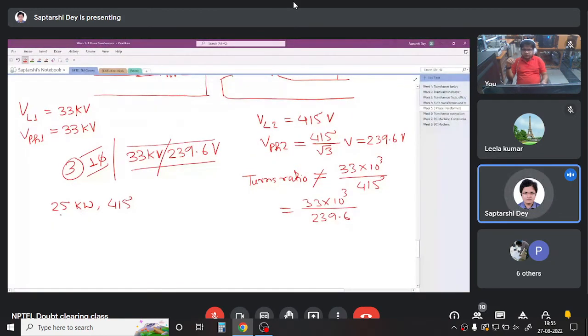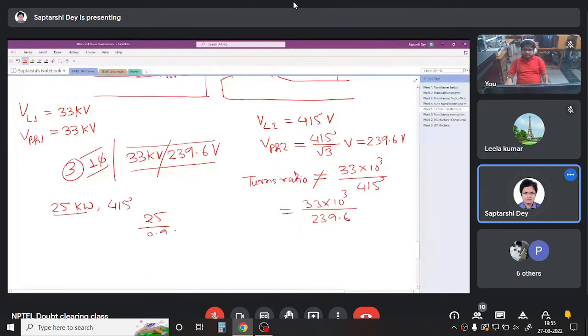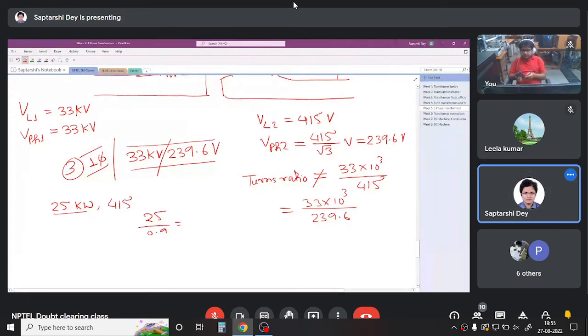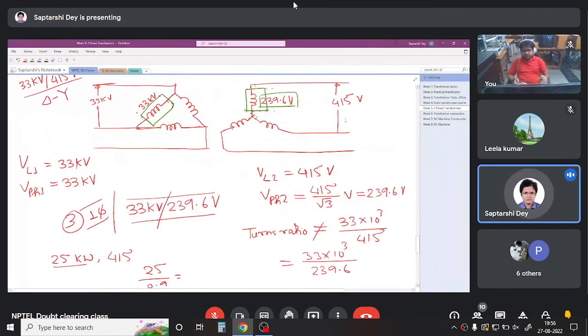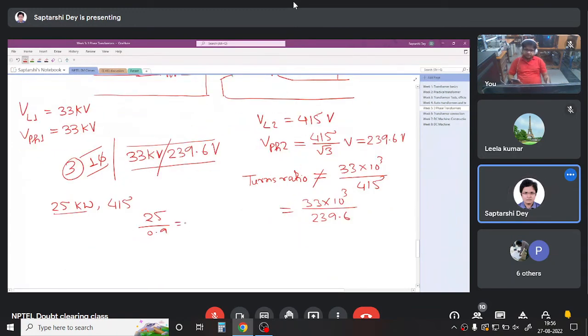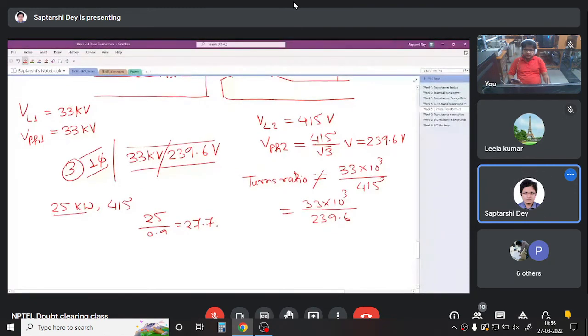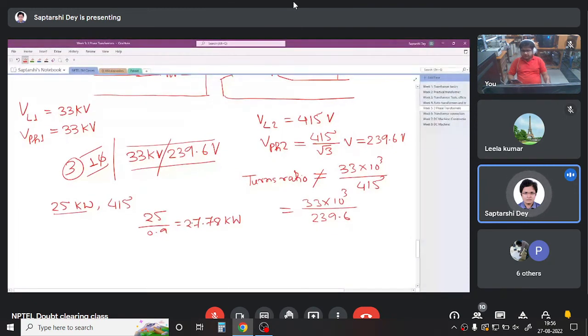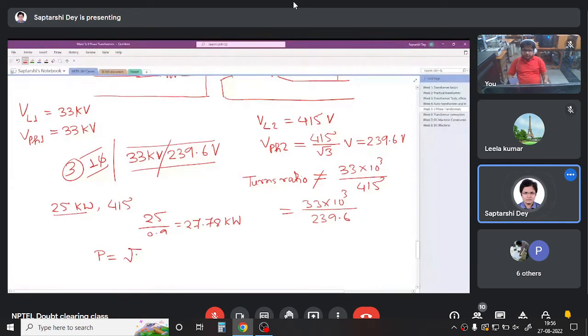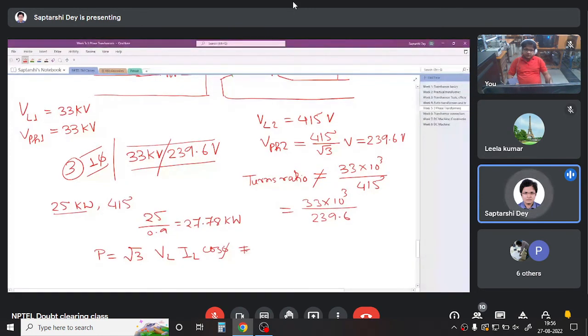So 25 kilowatt is the output, and it's 90% efficient, so the input is 25 by 0.9. This much power is being drawn from the transformer secondary. 25 by 0.9 gives me 27.78 kilowatt drawn from the secondary. Now we know that three-phase power is given by root 3 V line RMS, I line RMS, cos phi.